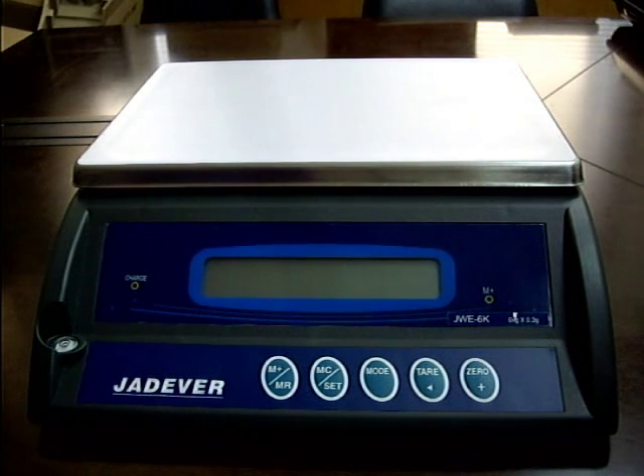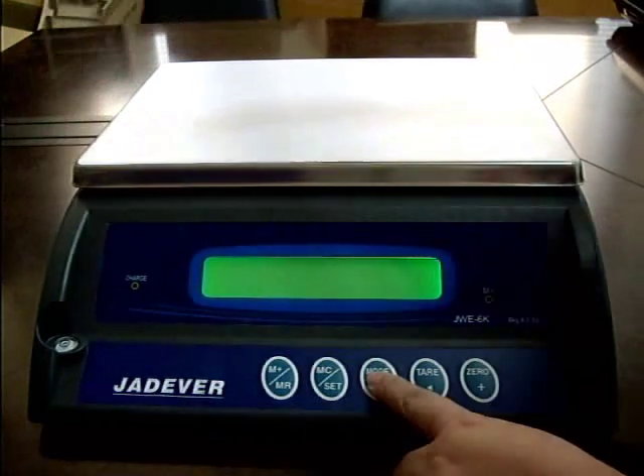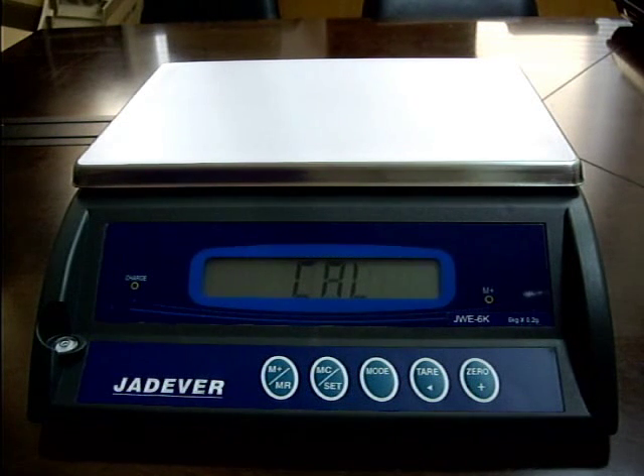JWE Series Calibration Procedure: Single Point Calibration. Press and hold key mode while powering on the scale. The screen displays CAL, then release the keys.